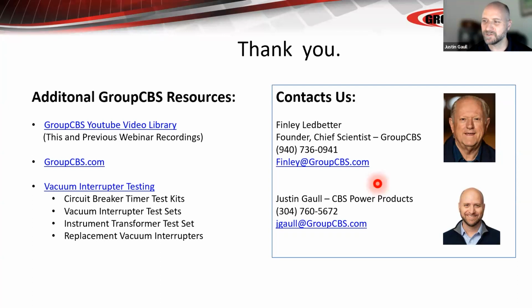All right, one more here. You may have addressed this, but which do you suggest: conducting a primary injection test or a secondary injection test for an existing circuit breaker? There again, do you have the results of a credible primary test in the last 5 years? If you don't, you have to have a baseline, and the baseline is a primary injection test. So you have to have a baseline. You have to know the entire trip system will work, or it did work at one time. We found electronic trip devices, when you take them apart, they didn't go through the soldering machine or were just jabbed onto the board. On the back, there's no solder. So basically, you have to make sure the system worked credibly in the not too distant past. If you do, and you have that from a credible resource, then a secondary test every so often is acceptable.